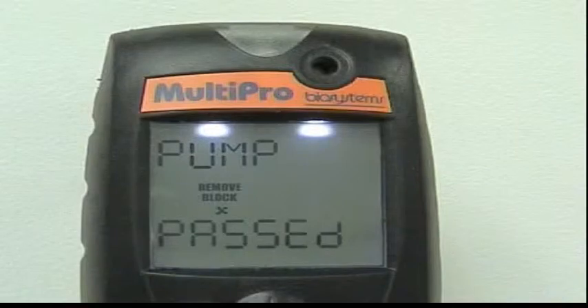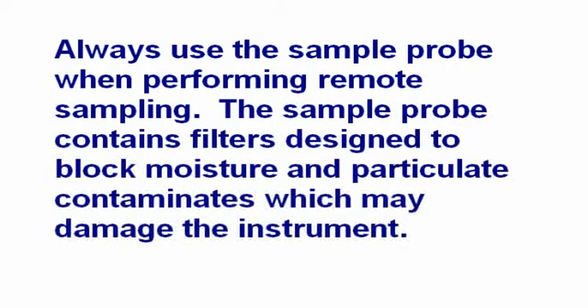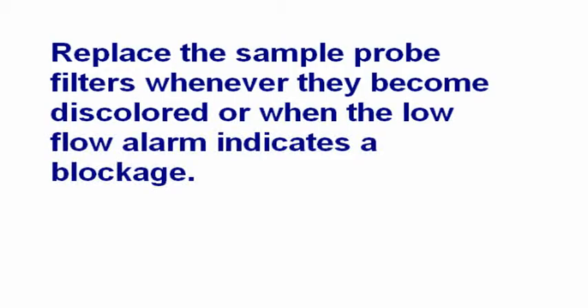Please note to always use the sample probe when performing remote sampling. The probe handle contains filters designed to block moisture and particulate contaminants, which may cause damage to the internal components of the instrument. Replace the sample probe filters whenever they become discolored or when the low flow alarm indicates a blockage.